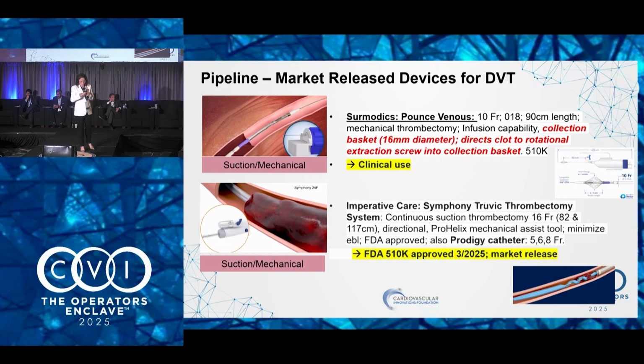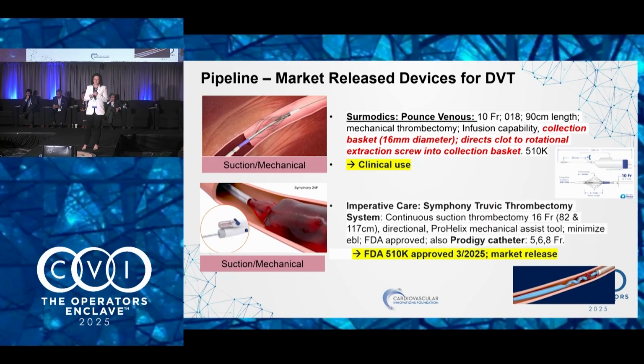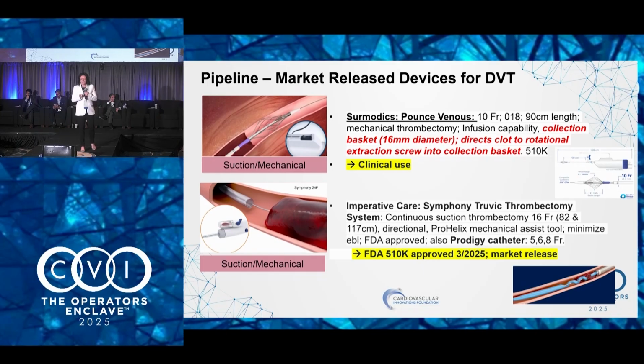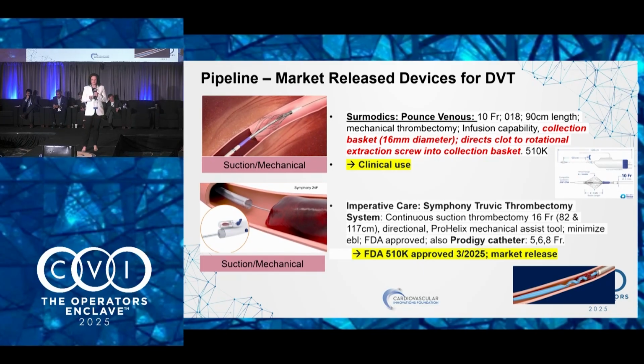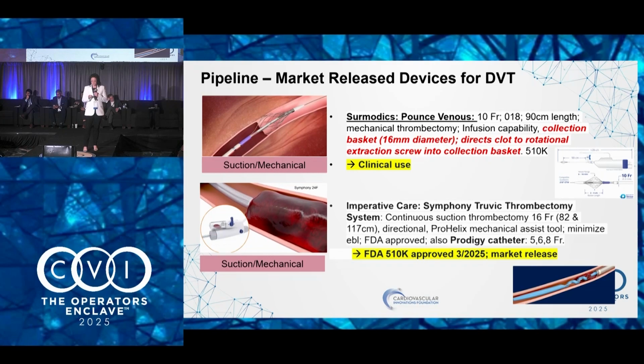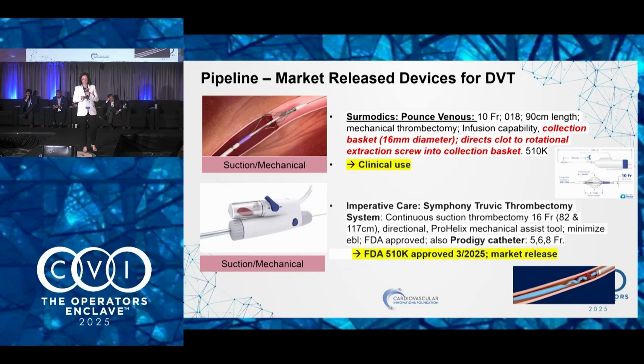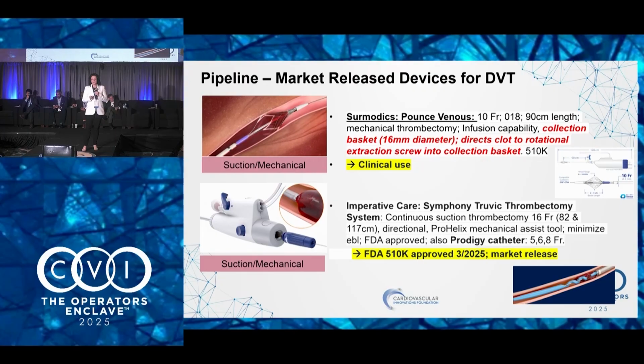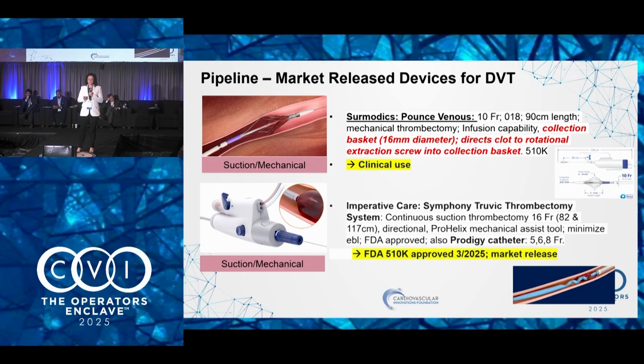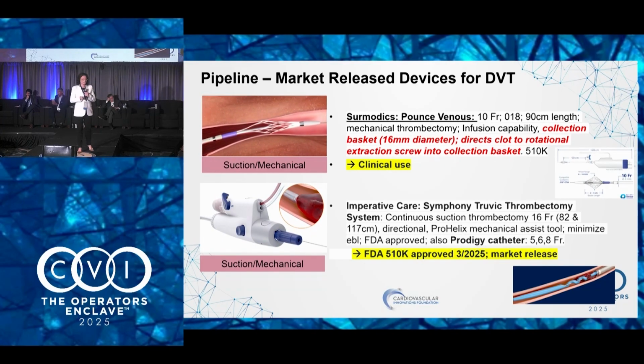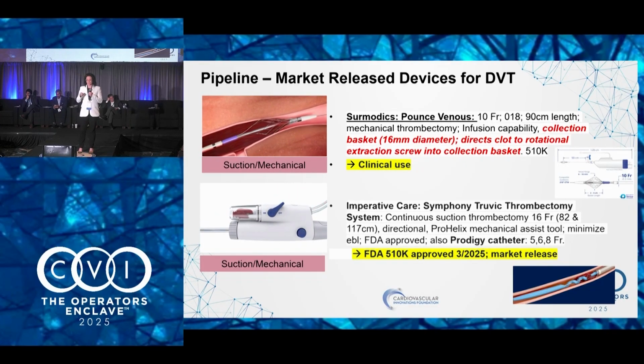Now coming on to what's in the market, the most recent one, Pounce, has been available since, I believe, last year. Surmodics Pounce venous thrombectomy is a 10 French, a bit smaller caliber, which is not usually available in most of the DVT devices, with a 90 centimeter length. It uses suction and mechanical approaches to treat DVT with infusion capability. The collection basket is 16 millimeters and directs clot to a rotational screw at the very top of the basket, which can then drill it into the device through a suction mechanism.